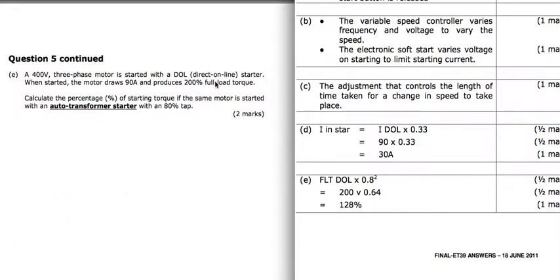There's the same motor, 200% full load torque. Calculate the percentage of starting torque if the same motor is started with an auto transformer starter with an 80% tap. Now this 80%, because we're only starting at 80% voltage, we're going to reduce this starting torque. And it's not going to be a direct reduction of 80%.